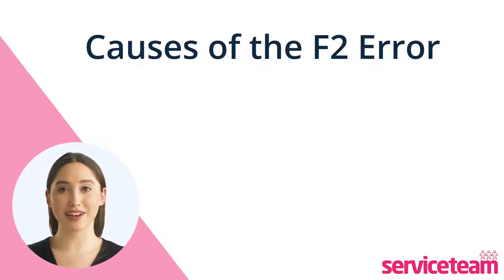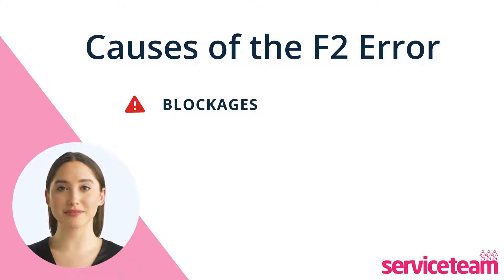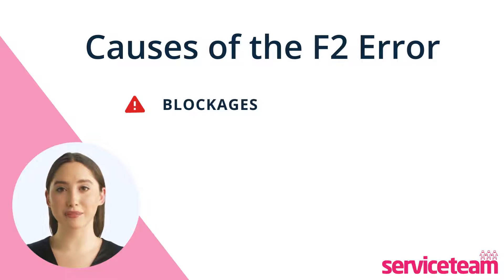Let's see what causes the F2 error. The main cause of the F2 fault is blockages in your heating system. These blockages can be because of the buildup of sludge, dirt, rust, or limescale. Sludge — a thick mix of debris, rust, and dirt — is common in many boilers. It gathers in the system, blocking pipes and disrupting water flow.